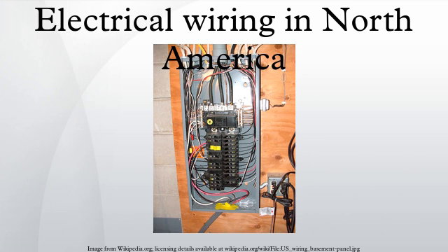Grounding of distribution circuits is a notable difference in practice between wiring systems of the United States and those of other regions. Since the early 1960s, wiring in new construction has required a separate grounding conductor used to bond all normally non-current-carrying parts of an electrical installation. Portable appliances with metal cases also have a bonding conductor in the flexible cable and plug connecting them to the distribution system. The circuit return conductor is also connected to ground at the service entrance panel only. No other connections from neutral to ground are allowed, unlike regulations in other parts of the world.